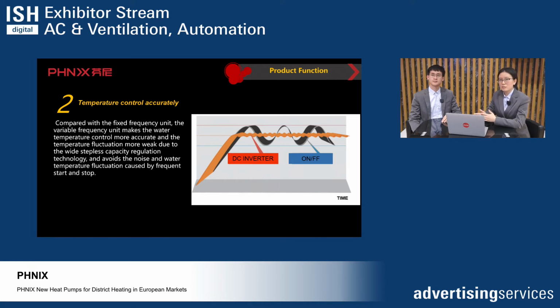And the second function is accurate temperature control, compared with the fixed frequency, which is the on-off unit. You can see in this picture, the temperature fluctuation is very big for on-off units. But for inverter units, you cannot see the difference clearly, right? Right. For these DC inverter units, the fluctuation is very small. It's very stable. Yes.